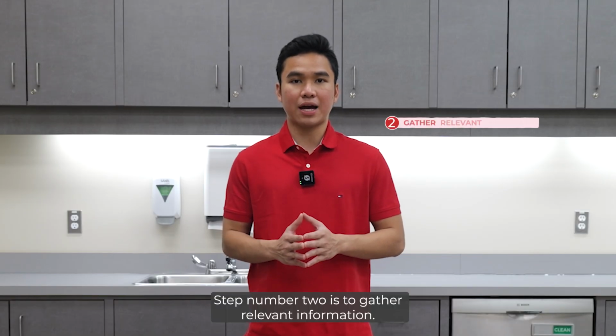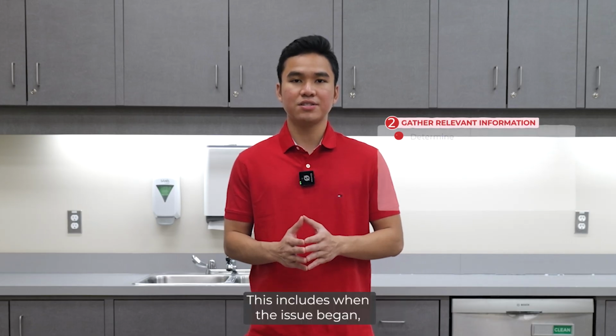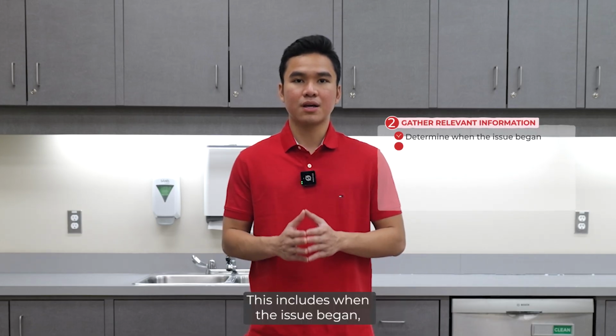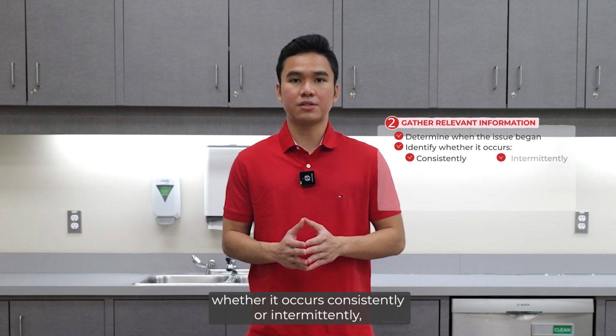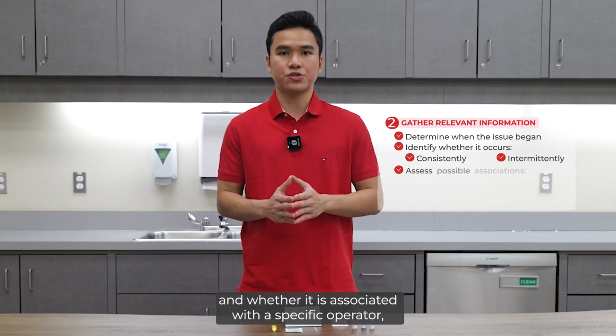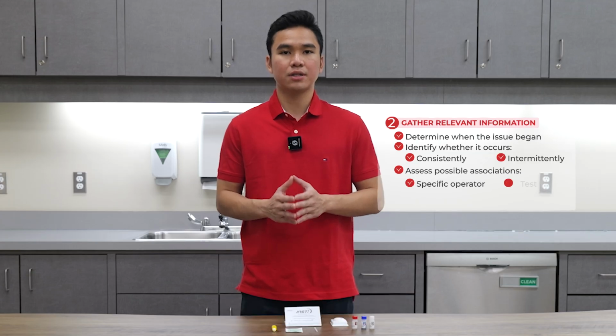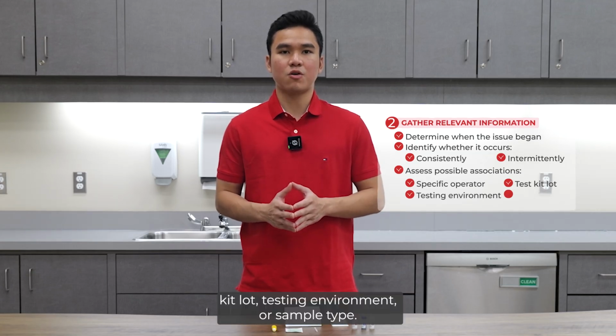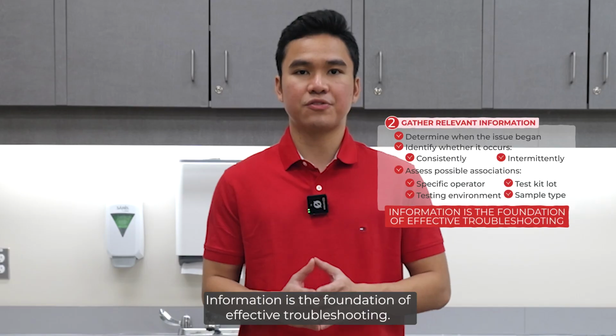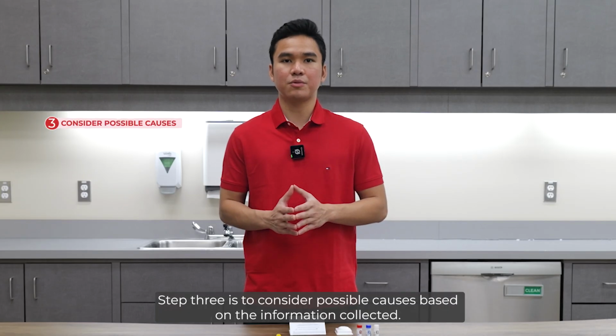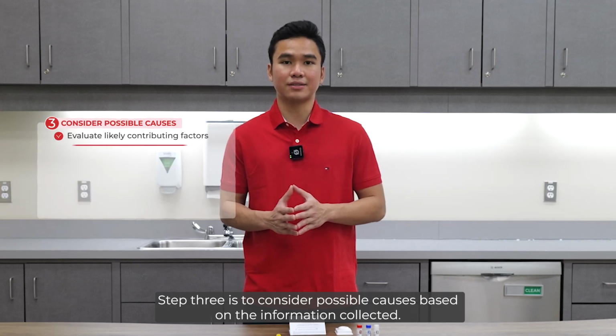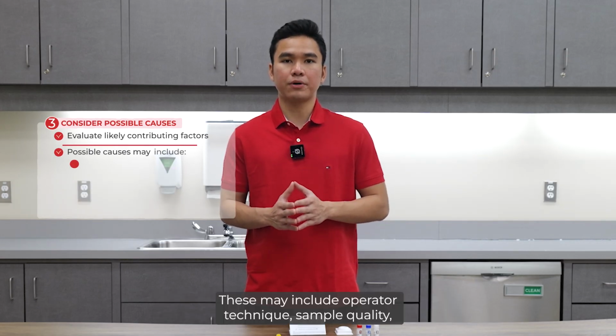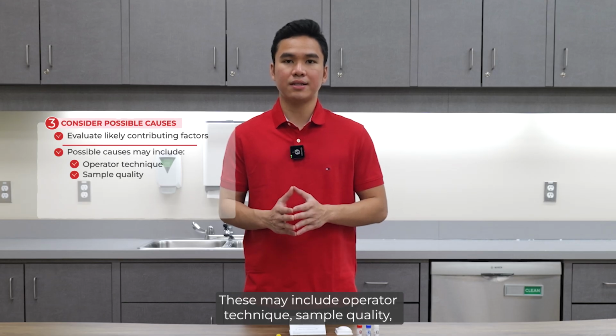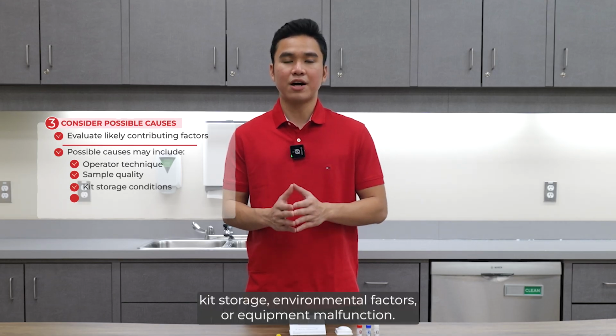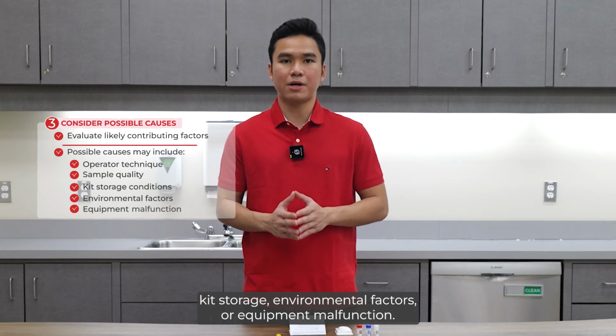Step number 2 is to gather relevant information. This includes when the issue began, whether it occurs consistently or intermittently, and whether it is associated with a specific operator, kit lot, testing environment, or sample type. Information is the foundation of effective troubleshooting. Step number 3 is to consider possible causes based on the information collected. These may include operator technique, sample quality, kit storage, environmental factors, or equipment malfunction.